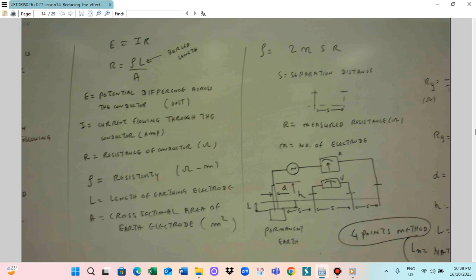Normally we put the earth bar electrodes, driven into the ground and separated by a distance. We put an equal distance between them, so with the number of electrodes and the measured distance, we can measure the earth resistance with the ammeter. So those things are influencing rho. In this case, we can use the electrode as the permanent earth. So this is the ground area, and this is the permanent earth.